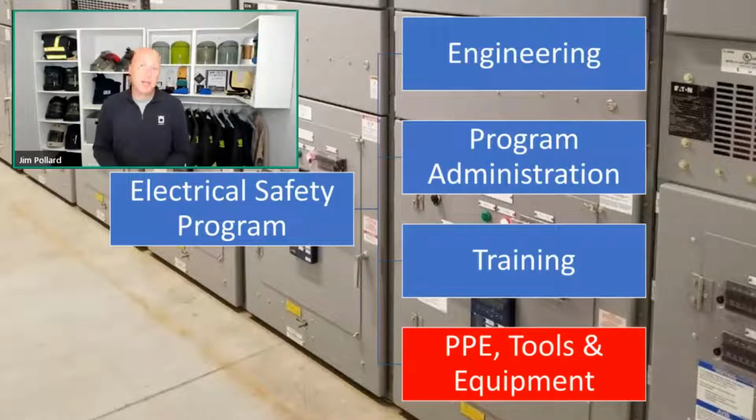In the hierarchical approach of how we mitigate risk for workers in the workplace with respect to their exposure to electrical hazards, the Arc Flash and Shock PPE is the last of those items. It's the very bottom of the list, but most often it's the most personal. It's what we have access to and is readily available, so it's most often discussed, but it is the least effective control to mitigate the hazards of electricity in your workplace. So please don't just jump right to protecting workers with PPE. You do need to follow the hierarchical approach of risk controls.